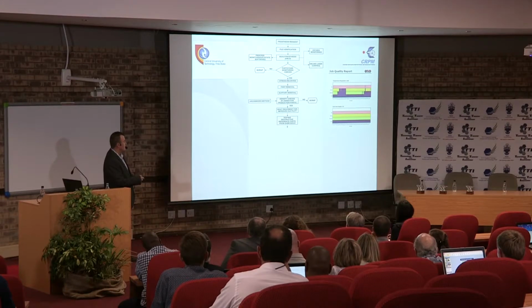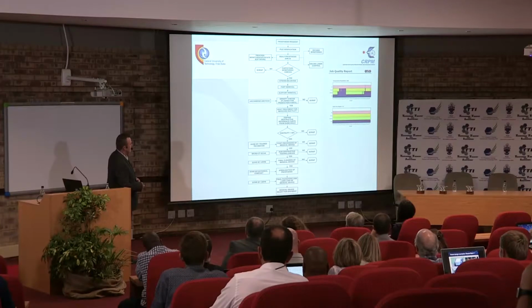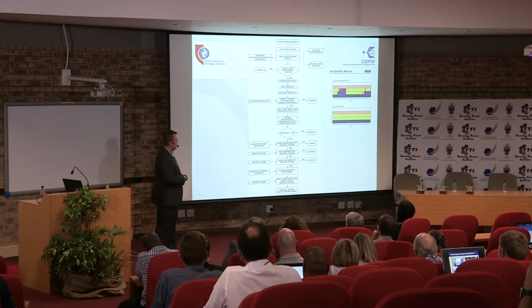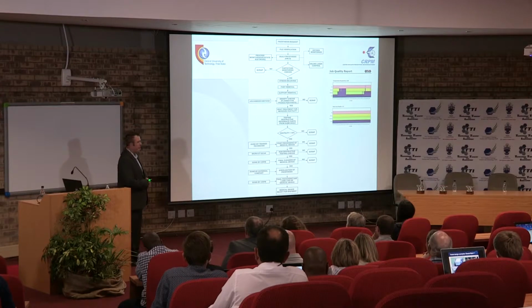If everything is good on this side, you go to the stress relieving, part removal, support removal. That's where the extra few days are coming, as well as the density checks and heat treatment to improve ductility, and that's why it's so long. You can see many steps. Even so, with all the implants, we are manufacturing destructive test components as well that we're sending out at this stage. It's still outsourced, but we purchased our own tensile tester so we can do it in-house. As grown, the ductility of the implants is around 2 to 5%, and we need to get it up to above 10%.